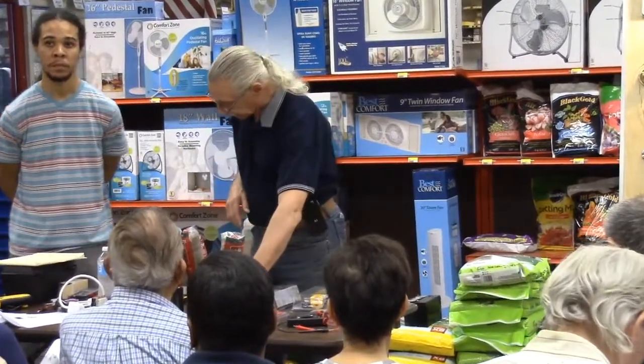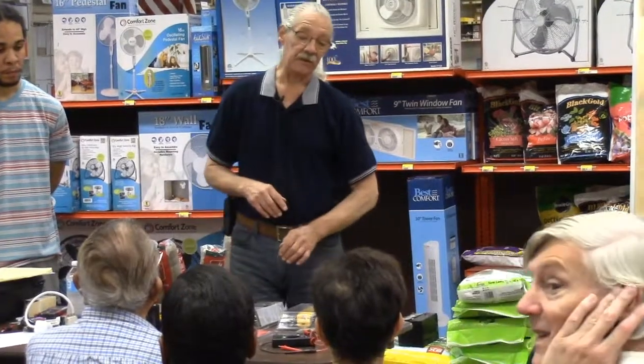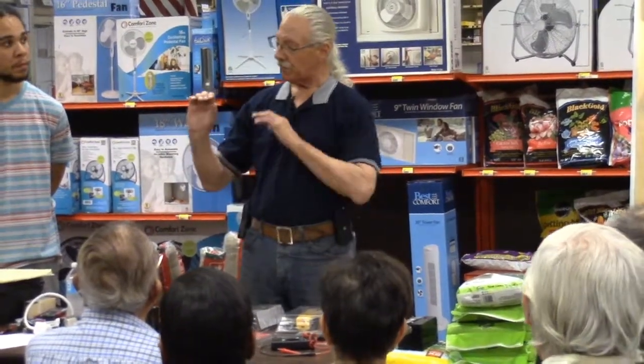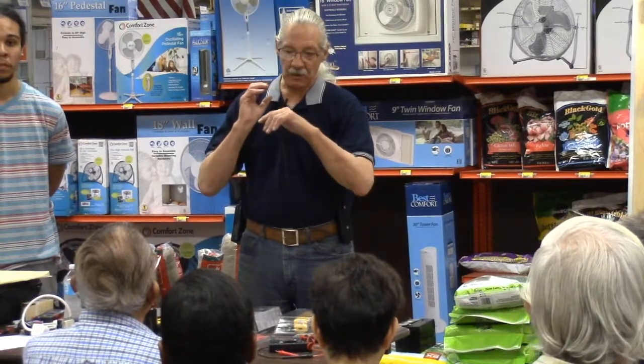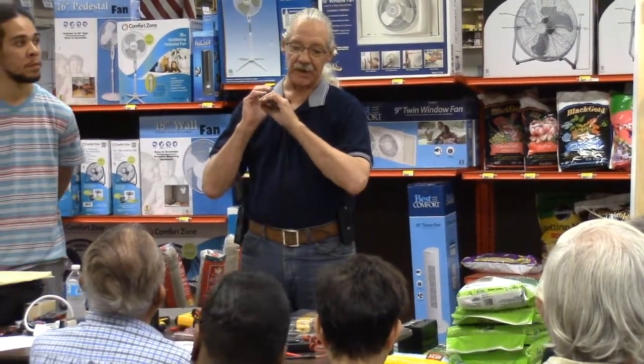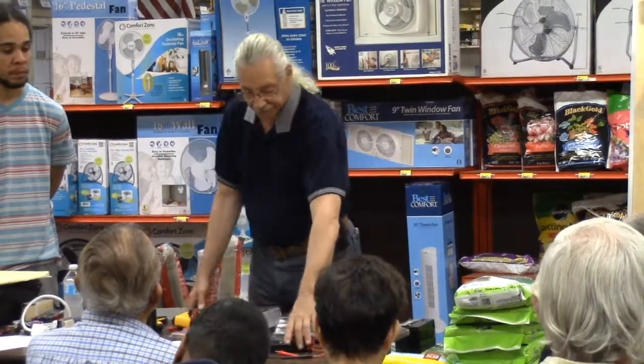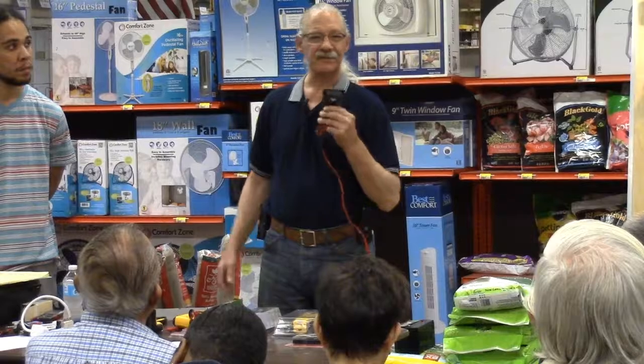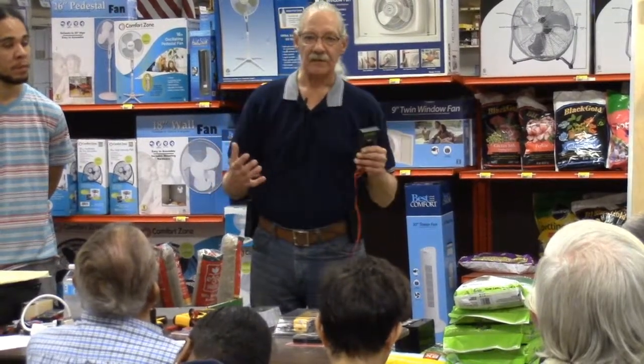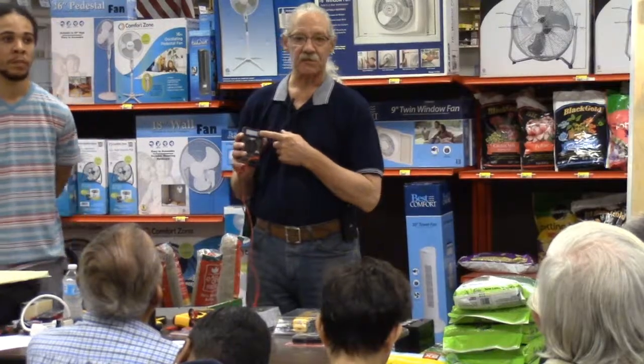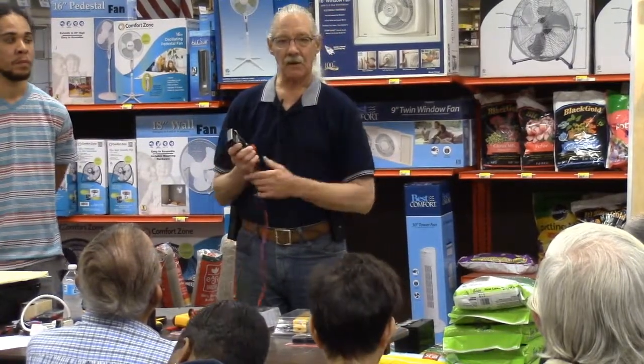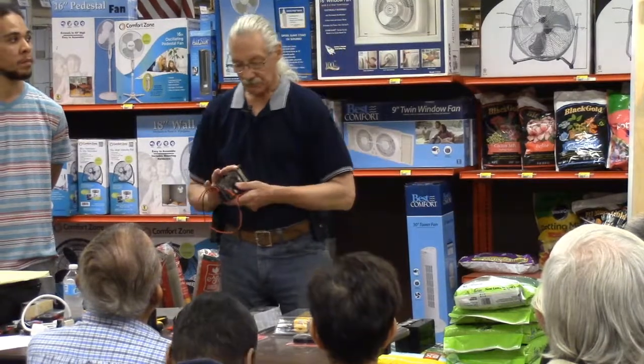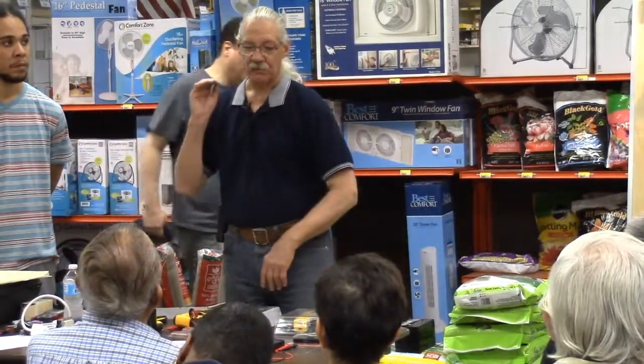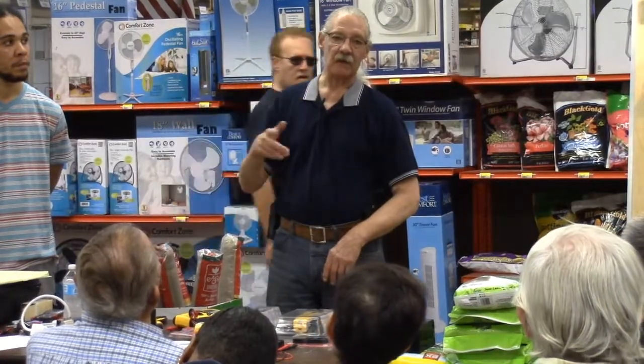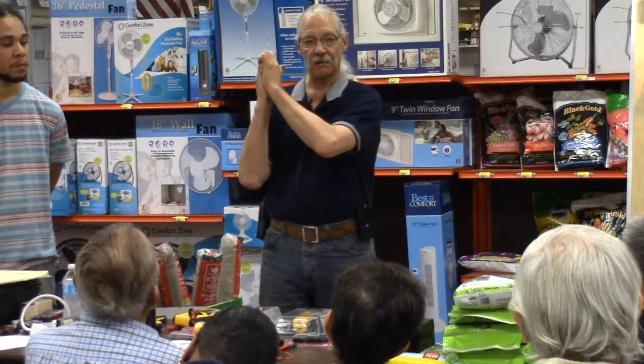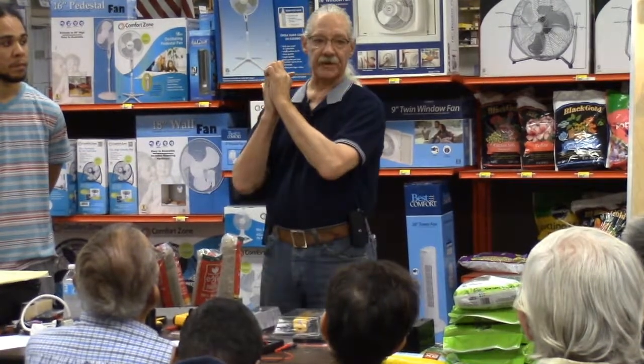Can you get induced voltage other places? Yes. If you have a conduit with a bunch of wires in it, and one of those wires is dead, and you're testing it with a meter, all of a sudden that dead circuit I know is dead gives me readings of maybe 50 or 75 volts, and I shouldn't be getting that. Well, when electrons move through the wiring, they create a magnetic field, and that magnetic field travels to other wires and gives a false voltage reading.